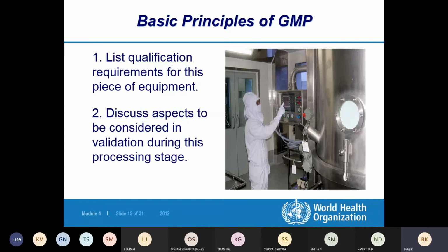Now, list of qualification requirements for this piece of equipment. You can see in this picture the equipment and the person working within the clean room, fully gowned, possibly in a sterile gown, with a tag hanging below - that's a simple calibration tag. There's one outlet and one SS handle with the tag. The person is operating the HMI, which is a kind of SCADA or computerized system that needs to be validated.